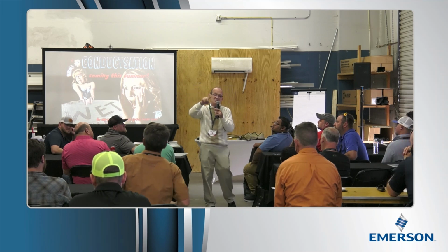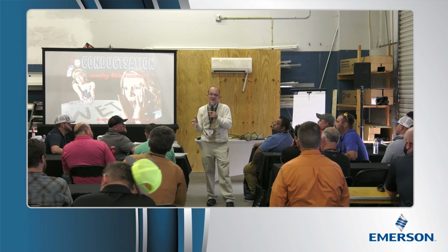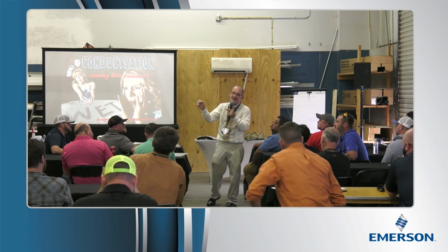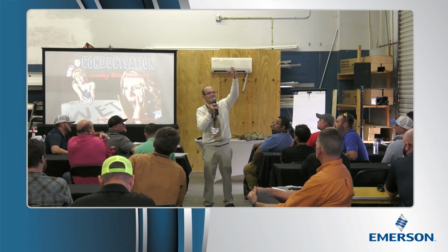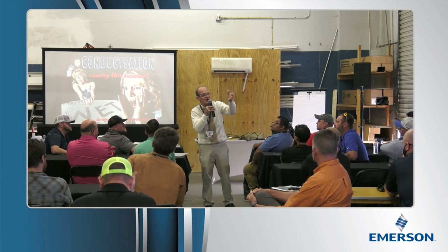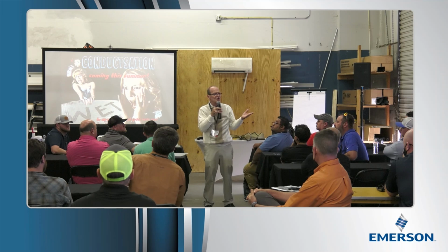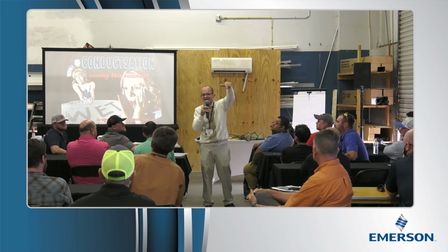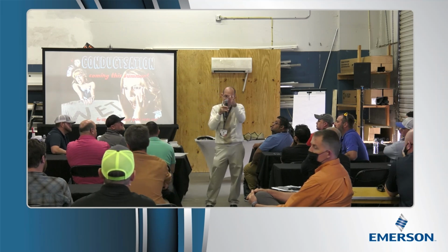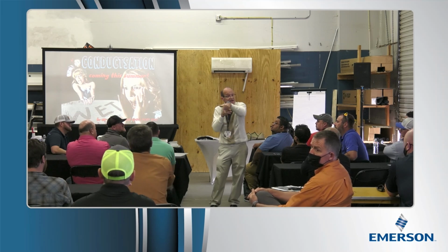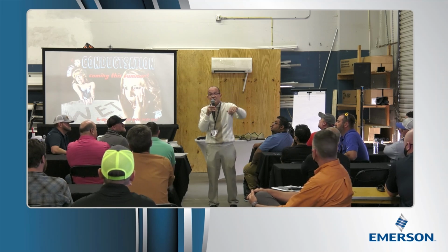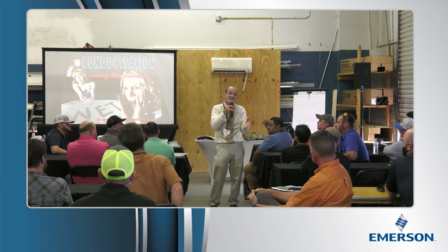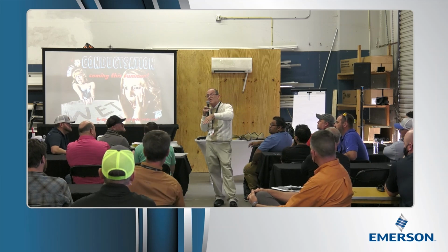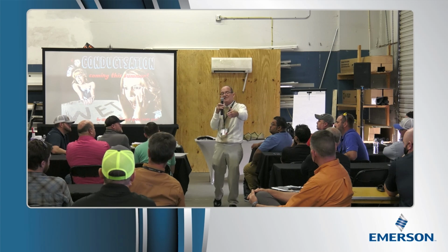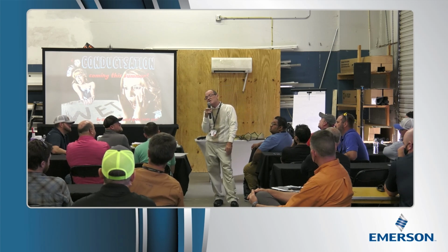If you've got a lot of bypass, which seems to happen on package units a lot, you get too much bypass when you put the cover on. There's also been cases where there's a little metal flange on the edge of the grill or the edge of the coil that doesn't seem to have a functional purpose, it just kind of hides the end bends. Well, that metal may be an air barrier to keep the air from going around. If you don't have it on there, or it rusts away, you're going to have more moisture because more of the molecules went around the coil and didn't condense. But that's the only thing you can do.